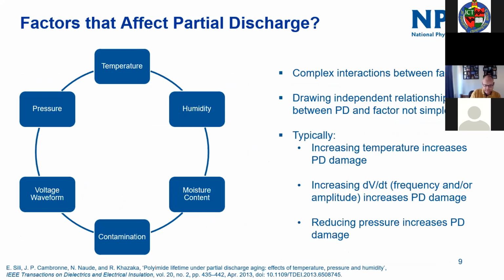The voltage waveform plays a large part in it. However, we shouldn't rule out that just because you've got a DC voltage you can't have partial discharge, because if you're switching that DC voltage, you've effectively got a very slow square waveform. So you will potentially get partial discharge every time you turn that DC voltage on and every time you turn it off.